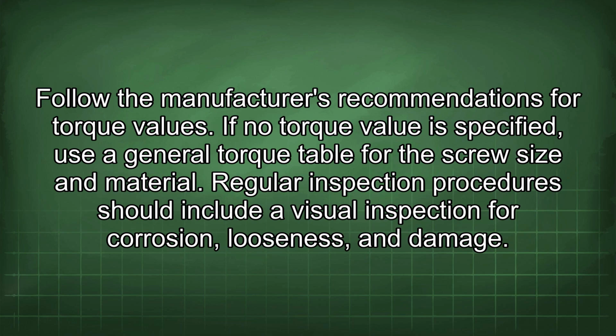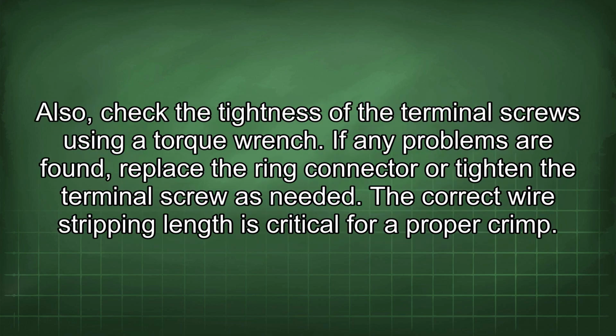Regular inspection procedures should include a visual inspection for corrosion, looseness, and damage. Also, check the tightness of the terminal screws using a torque wrench. If any problems are found, replace the ring connector or tighten the terminal screw as needed.